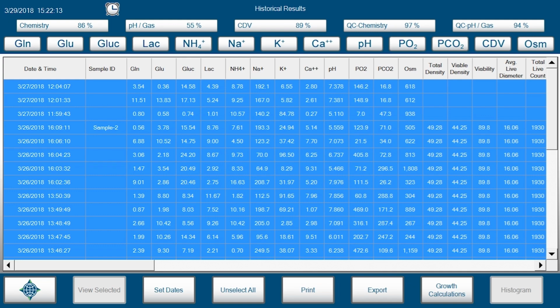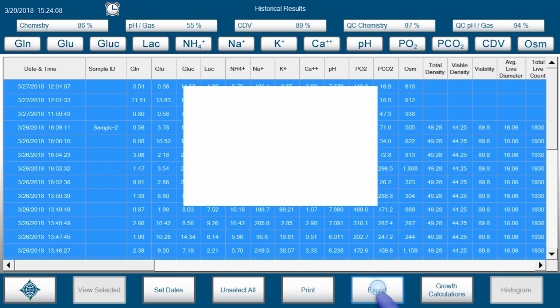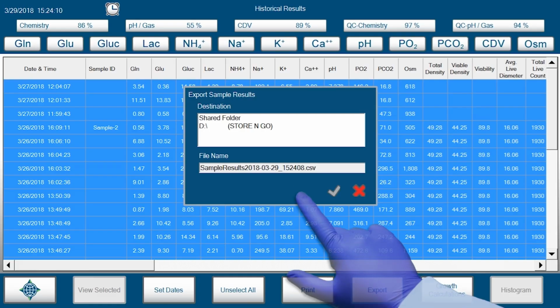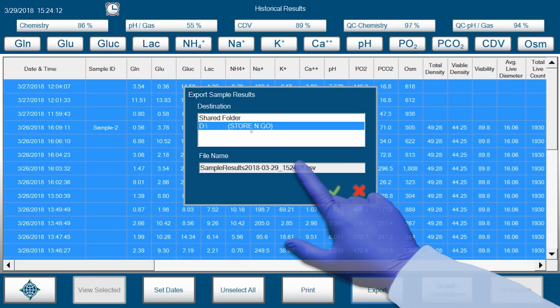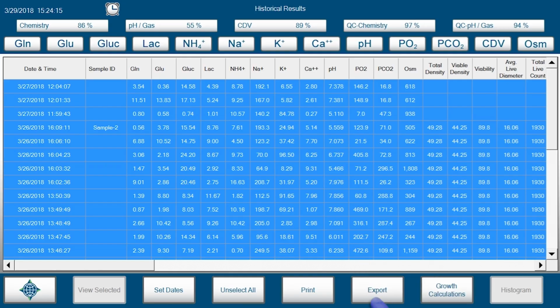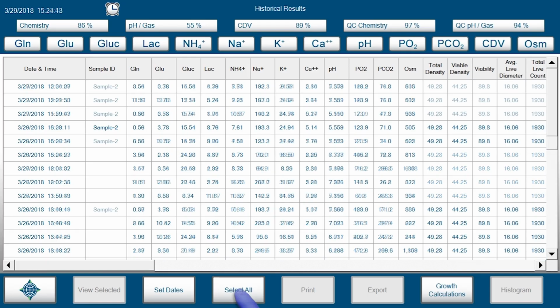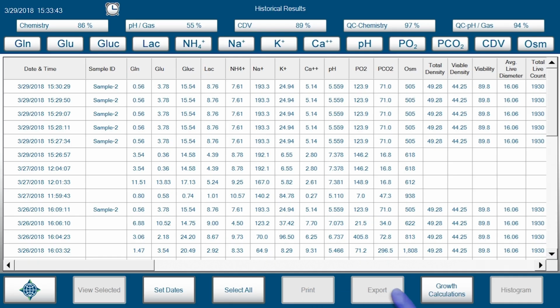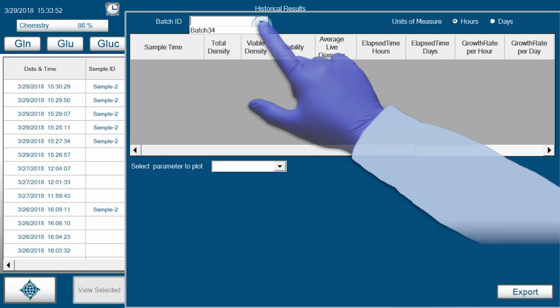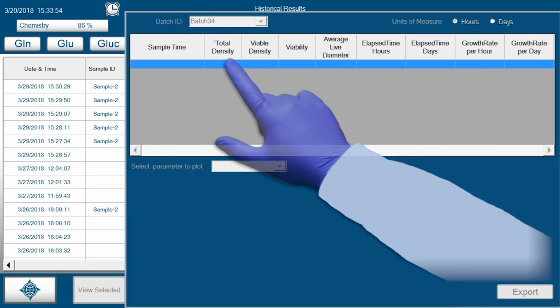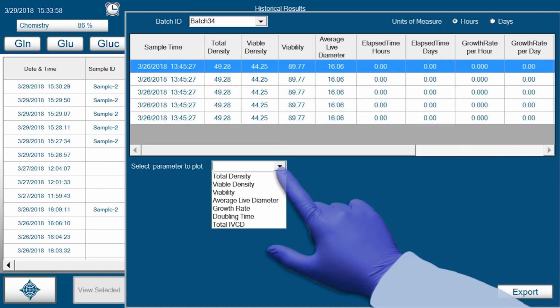You can export results in CSV format by selecting the Export button, then selecting the location you would like to export to. Both PDF reports and exported CSV files can be exported to an external USB drive or to the Flex 2 Bridge computer. Growth calculations are available if samples were assigned a batch ID. If you select Growth Calculations, you will then need to select which batch ID you would like to trend, and select the parameter you would like to see on the chart.